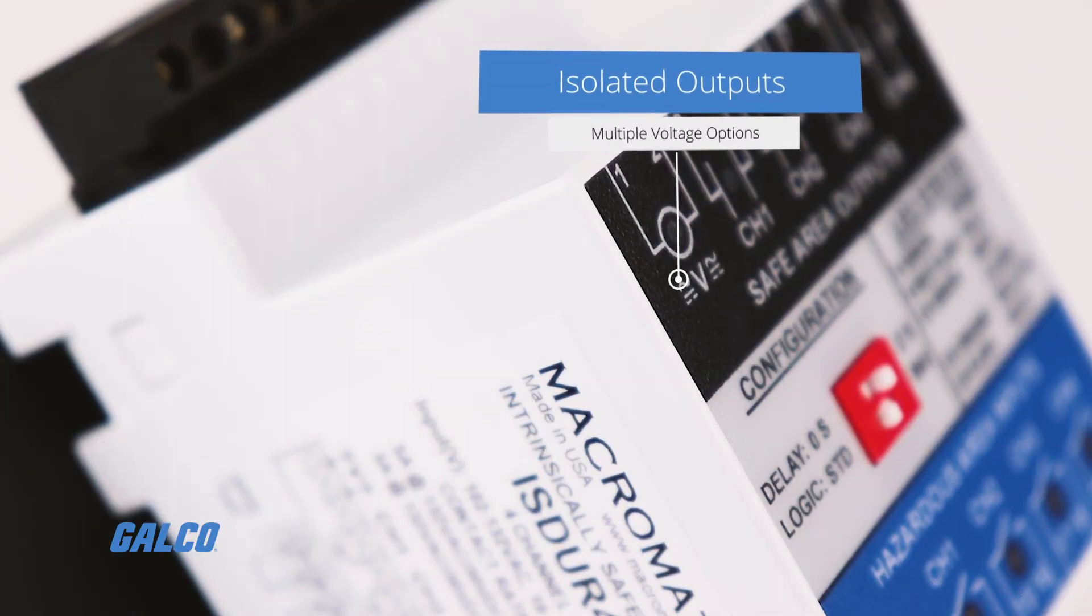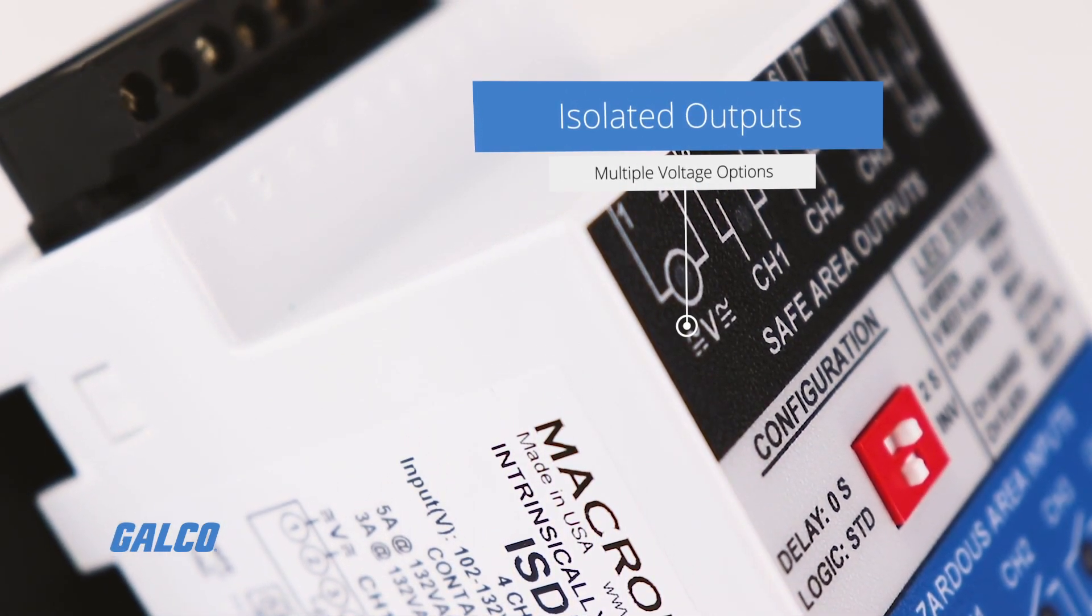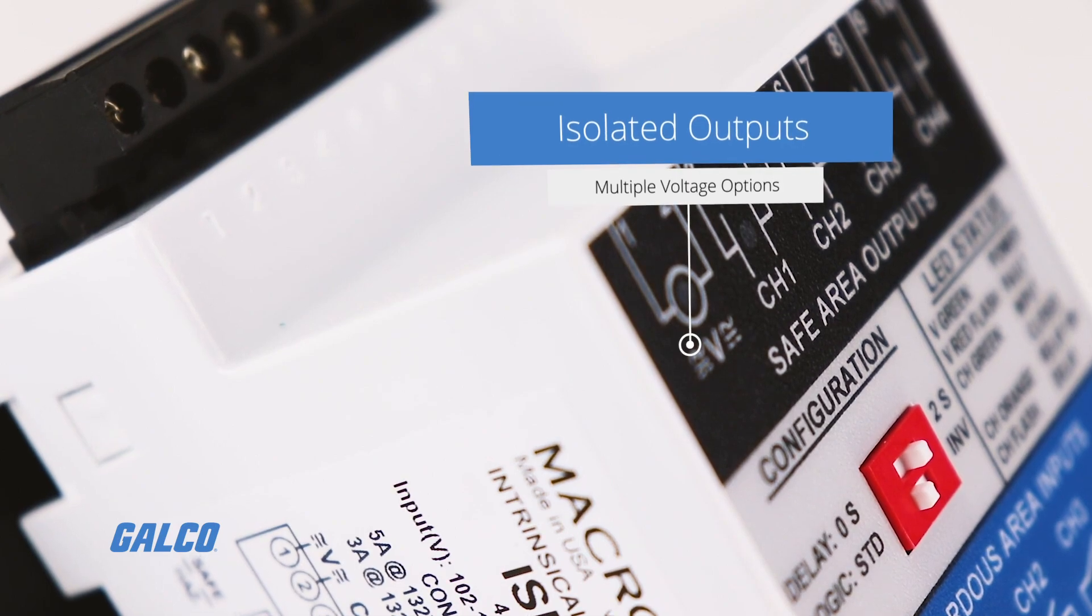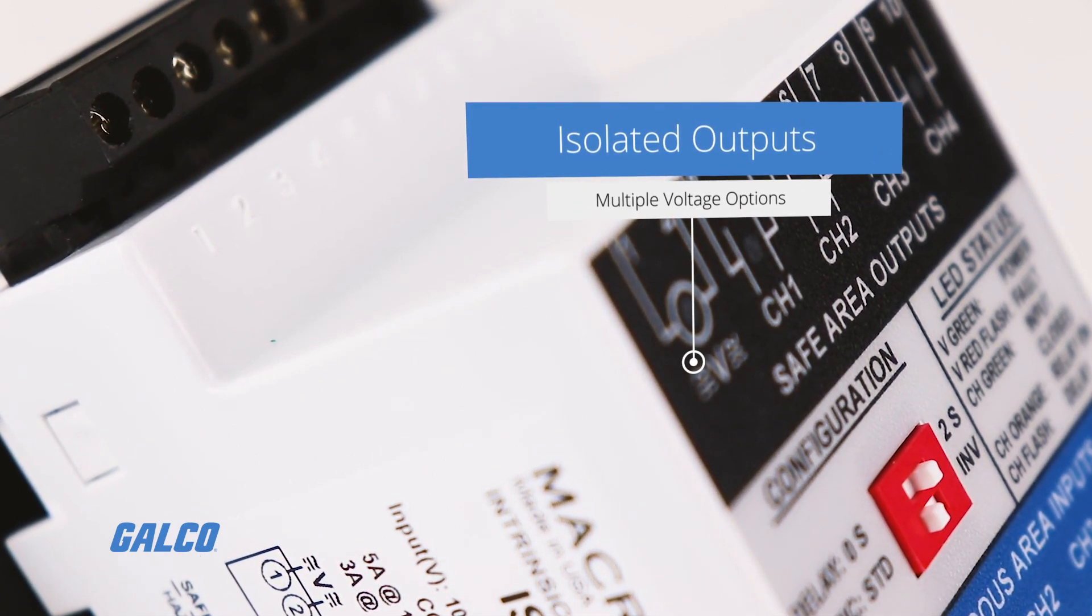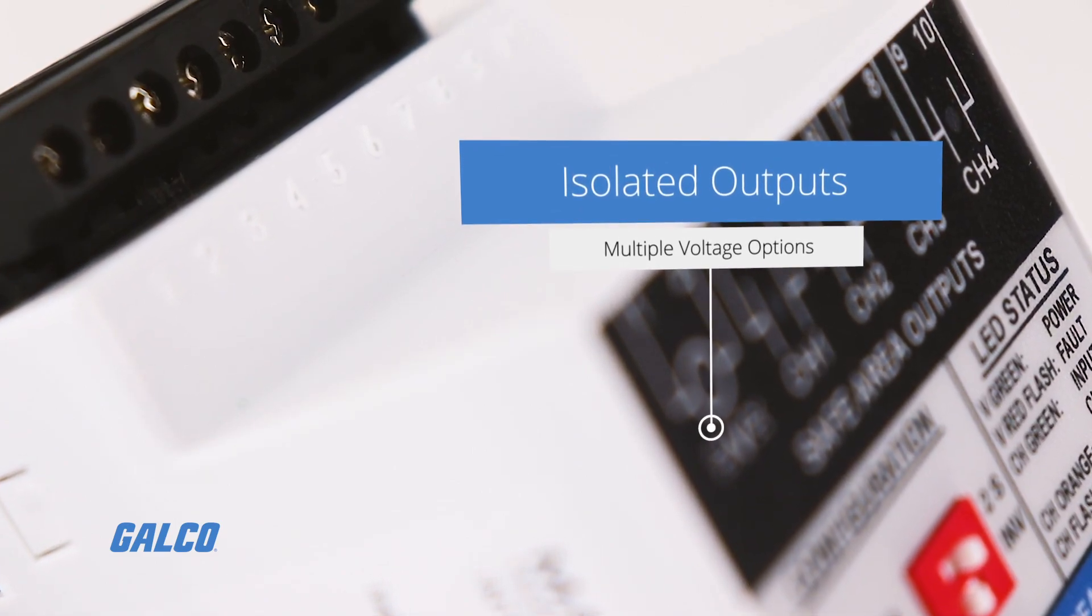Each output relay has two terminals for isolation from the others, allowing outputs to be at different voltages such as contactor coils at 120 volts AC and an alarm circuit at 24 volts DC.